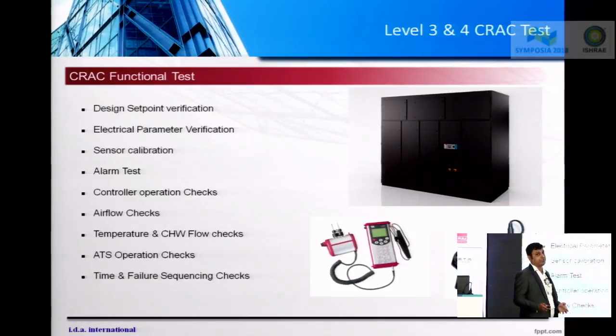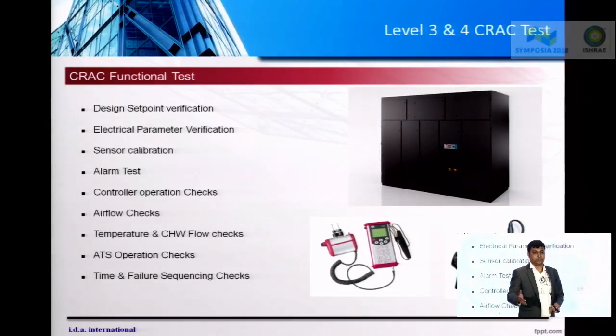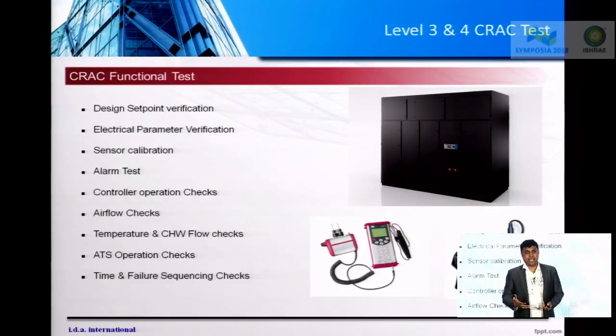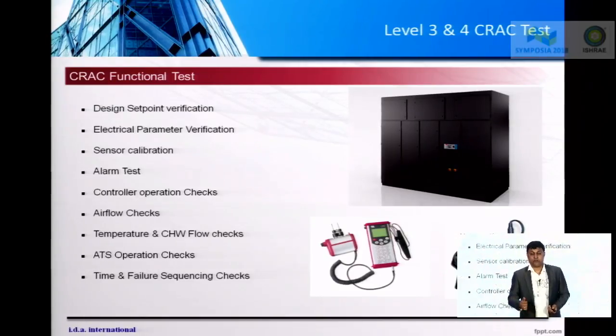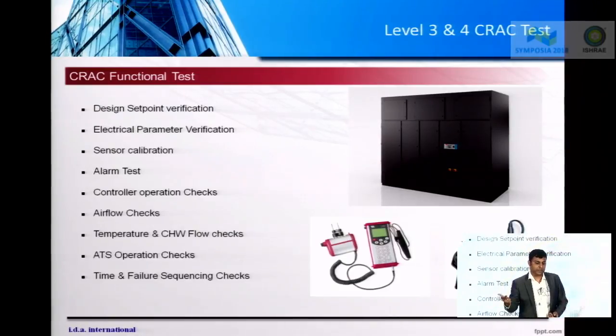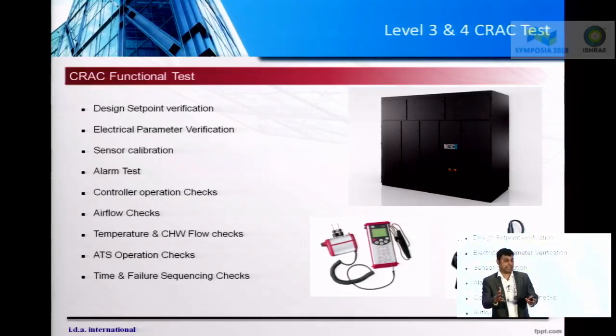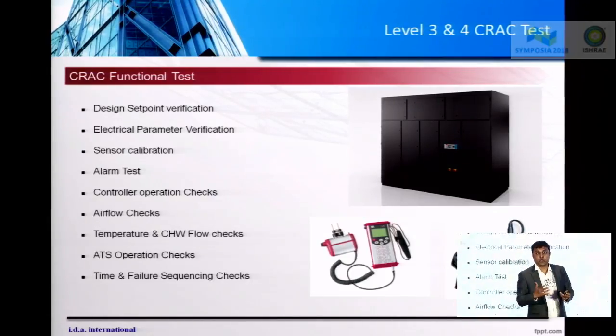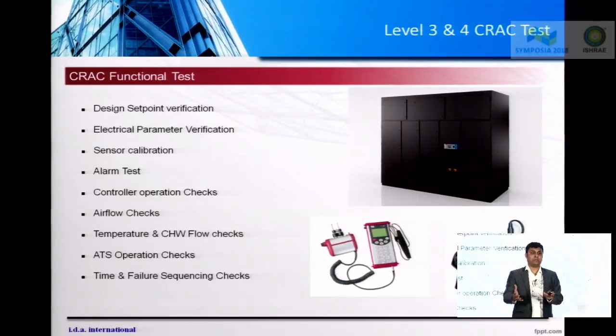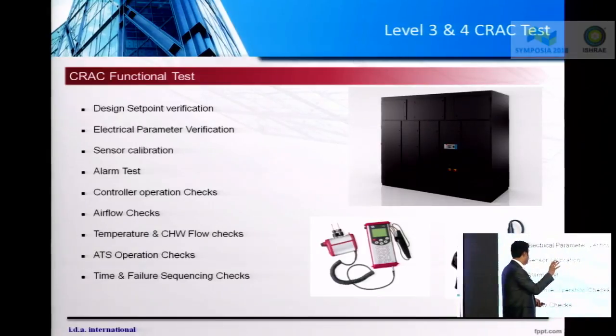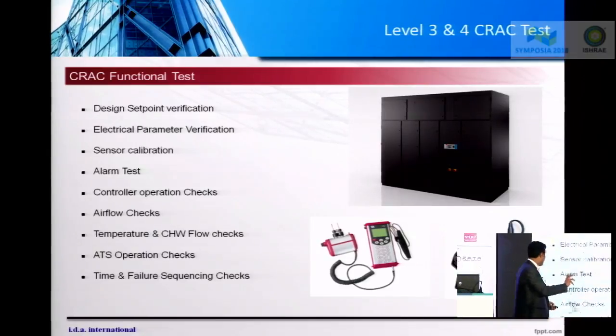Controller operation checks. Now, the CRAC unit has an inbuilt program, right? You can verify the logic of how the cooling gets triggered, how the heating gets triggered, how the humidification or dehumidification gets triggered. So you have to verify this logic. For some of the CRAC units which are with dual coil, you can verify some extra logics like how the dual coil works in an alternate mode, in parallel mode, or in cascade mode. So this is part of the performance verification, which is controller operation checks.